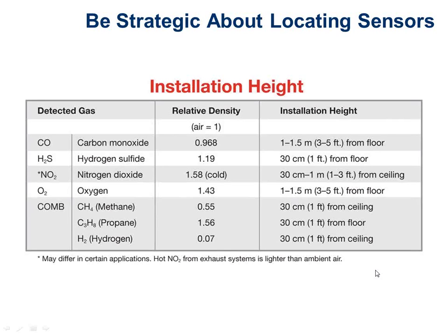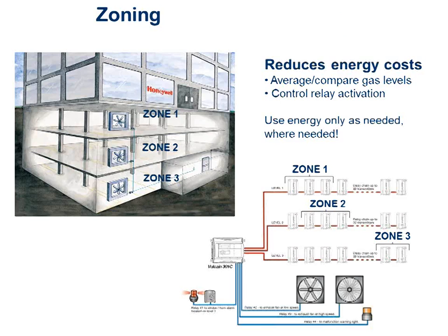The more CO I have in the parking garage, the faster I speed up the exhaust fan, which moves more air through the whole building assembly, which clears the CO out faster. And then as cars are not driving around, the CO level goes down, I slow down the ventilation fan, right? If I don't do this, my other choice is to run the ventilation fan 24/7, which is extremely expensive, right? But if I know vehicles aren't driving very much right now, and I have less CO in the air, I can slow my fans down, right? So in the morning when everybody comes to work, yeah, I got to ramp them up a lot. But then when they're all at work, I can ramp them down lower because there's hardly any vehicles driving around.